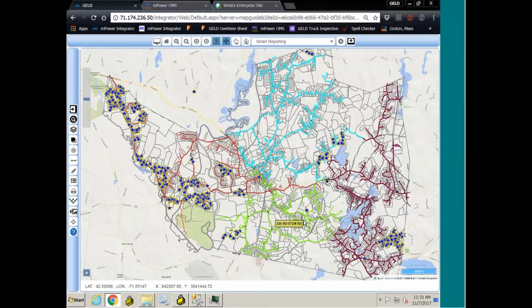Without having the data, it's hard to make the decisions. Like if one of these houses or one of these houses had been the first to call police dispatch, and you send your lineman here first, it actually turns out this area up here had one of the hardest outages. It actually took one crew 4 hours to get this packet at the end put back together. And this star right here took 1 crew 4 hours to deal with. So if you get your crews tied up in the wrong places, everybody else suffers while the work's being done.